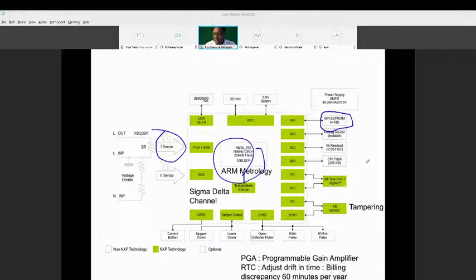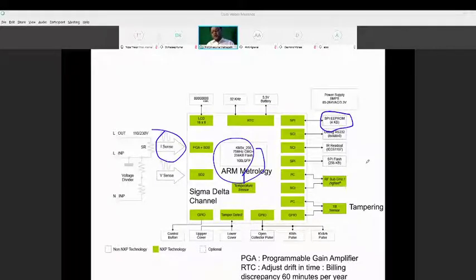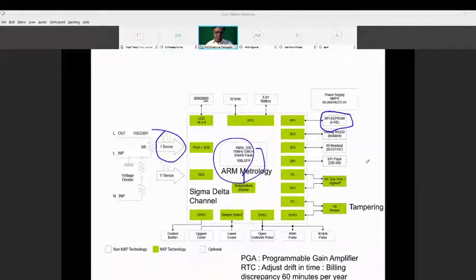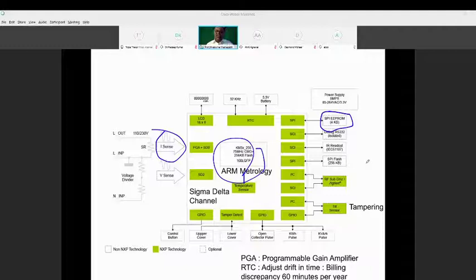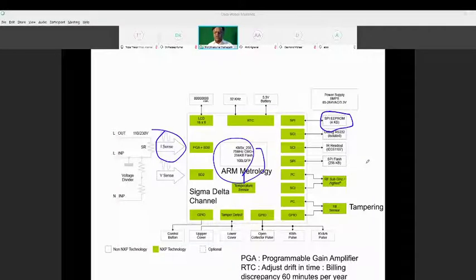There is an EEPROM - electrically erasable programmable read-only memory. You can program your billing structure and change it every year or every six months. Nowadays everything is done online - you log into the system and change the program. You can change the tariff or any information. There is also an infrared reader. Earlier, a person used to come with an infrared device to read the meter reading without even looking at the LCD. He would beam the infrared and take the sensor reading.